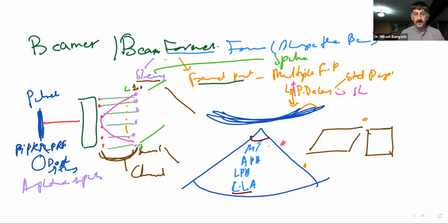Now, we may also want to focus at this depth here, and we also want to focus at this depth. What the beamformer will do is first send out beams that are going to focus at this shallow depth here. That's all controlled by the beamformer. How does it do that? Greater phase delay. And after that it goes to the deeper focal point and focuses at that. How will it do that? Shorter phase delay. So it alternates, but it happens so rapidly that we will not be able to detect it. Clear?